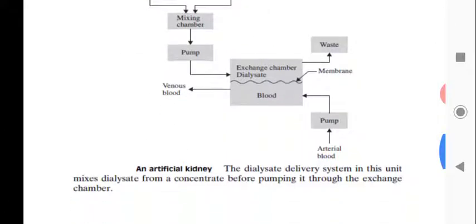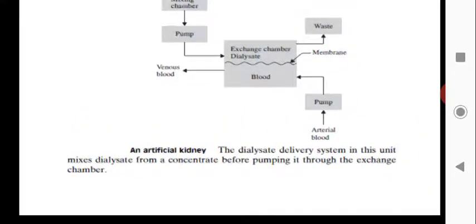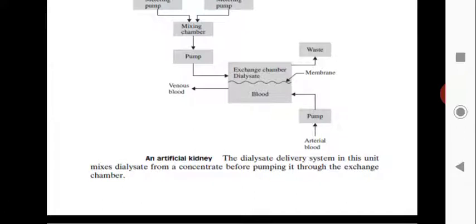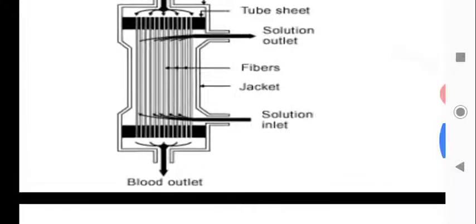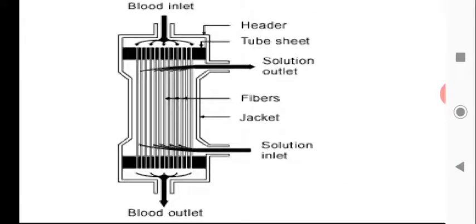The arterial blood is pumped through a roller pump and enters the dialyser as blood inlet, while the outlet blood goes to the venous blood return. The dialysate delivery system in this unit mixes dialysate from a concentrate before pumping it through the exchange chamber.